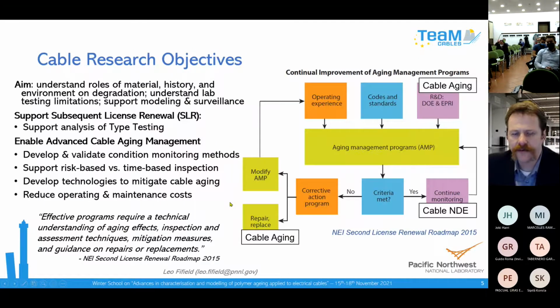So the objective of our research that's funded by the DOE is to understand the effects of the material systems, the materials in the cables, the histories of the cables, and the environments that they're in. Some places in the plant they're going to be exposed to gamma radiation, some places elevated temperatures. To understand those effects on the degradation of the cable system, and specifically the polymer insulation. We also seek to understand the limitations of accelerated aging in the laboratory, and to support predictive modeling of the remaining useful life of cables, and the condition and understanding signals from condition monitoring.